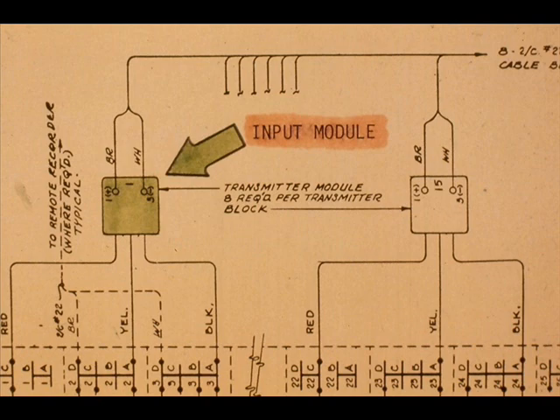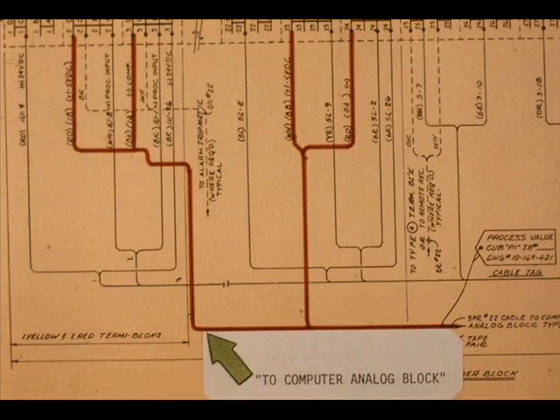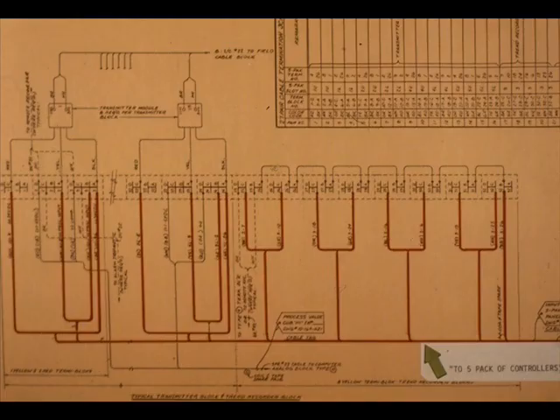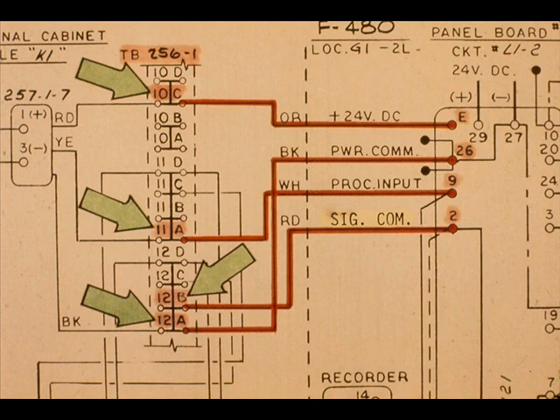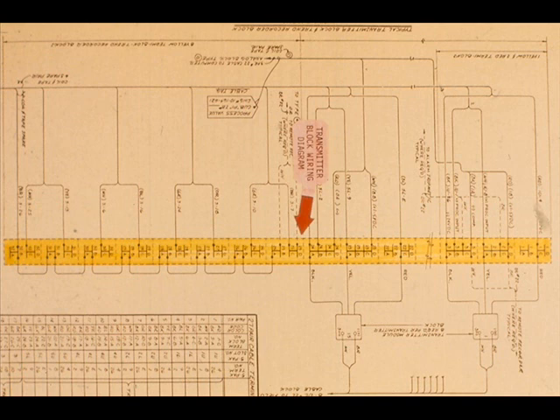Examine the terminal block wiring diagram. Notice the input modules and the 2 cables. One cable goes to the computer analog block. The other cable goes to a 5-pack of controllers in the panel. This is the cable we will discuss first. Our loop diagram shows that terminals 10C, 11A, 12B, and 12A connect the transmitter block to the controller. Look at the terminal block wiring diagram. Terminals 10, 11, 12 are not shown. How will you know which pairs to use?